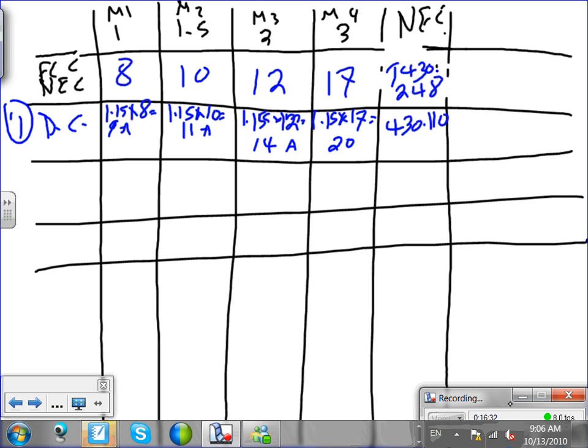Okay, now these are the calculated amps. Up to this point, this is my calculated amps. You're going to find the actual size of a disconnect. You're going to go to DeWalt, if you have DeWalt, page 3-12, sizes of disconnects. What's the smallest size of disconnect I'm going to load then? 30. Page 3-12, and this will be a 30 amp.